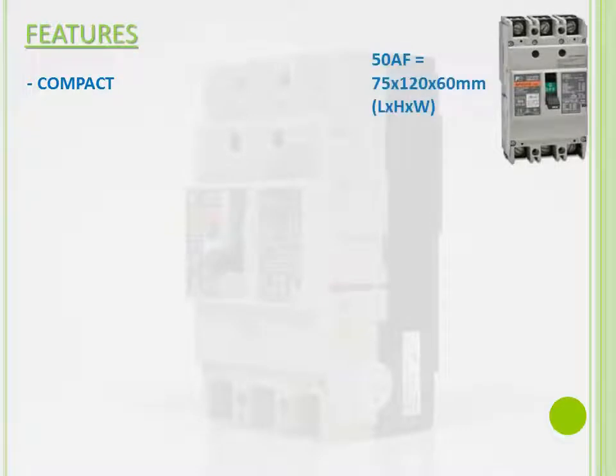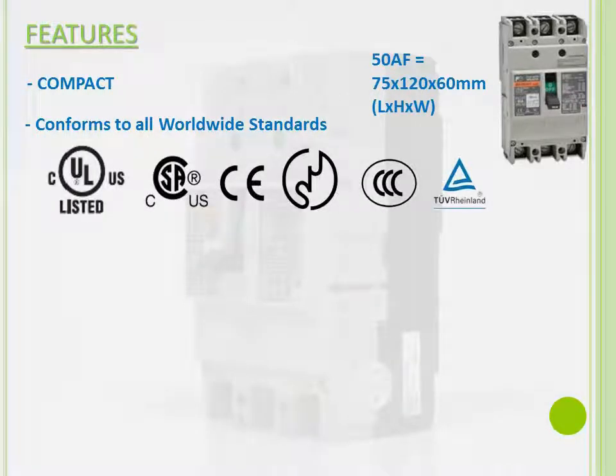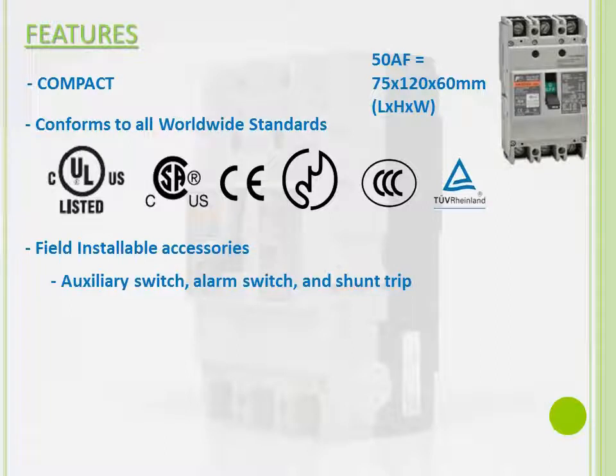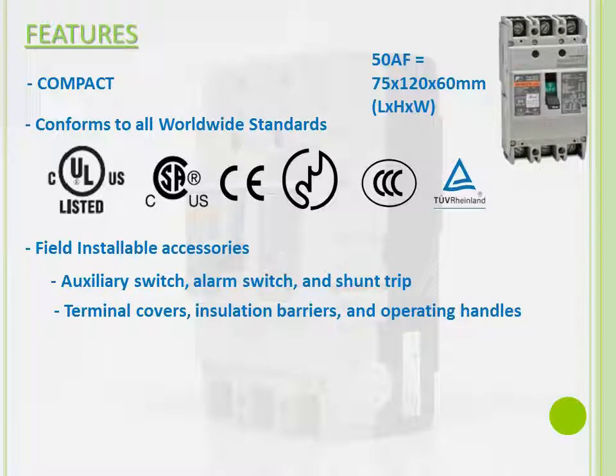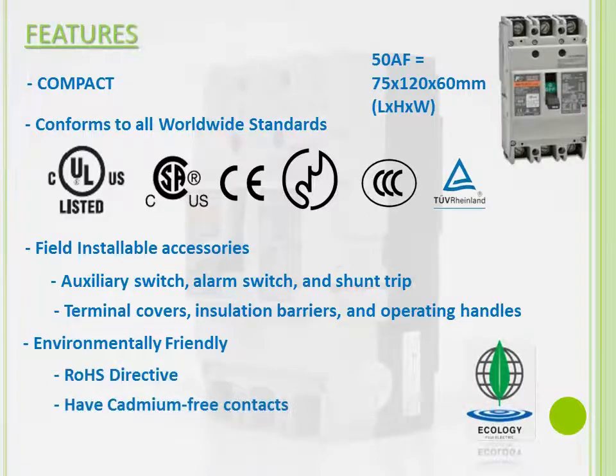Now let's look at the features for our G-Twin breakers. Our G-Twin breakers are compact, with our 50 amp frame coming in at 75 by 120 by 60 millimeters. They also conform to all worldwide standards, such as the UL, CSA, CE marking, JIS, CCC, and TUV. We also have field installable accessories, such as auxiliary switch, alarm switch, and shunt trips as internal accessories, and terminal covers, insulation barriers, and operating handles as external accessories. Our G-Twin breakers are environmentally friendly, conforming to the RoHS directive, and have cadmium-free contacts.